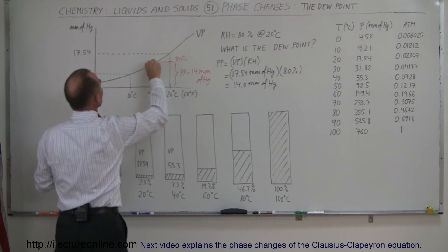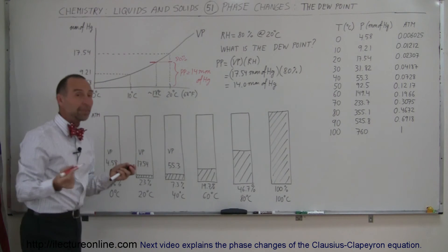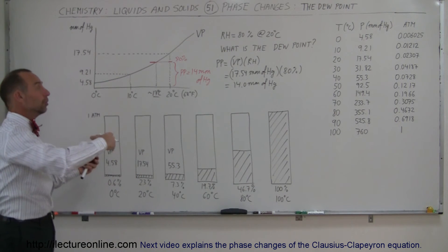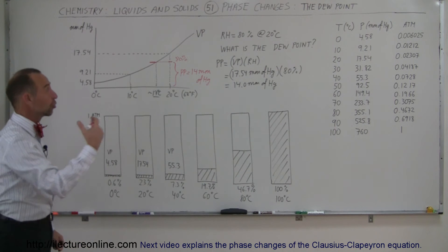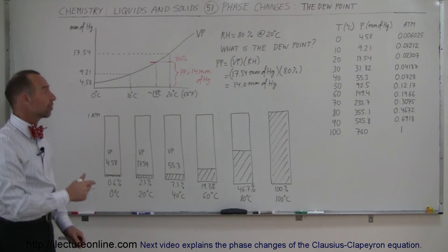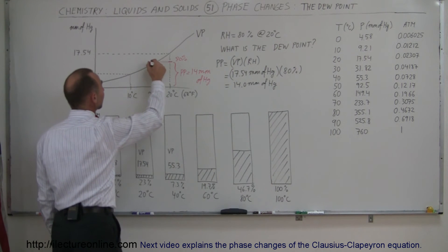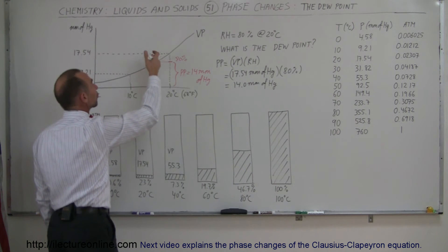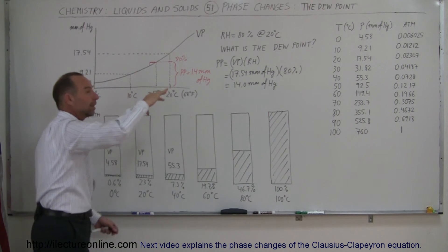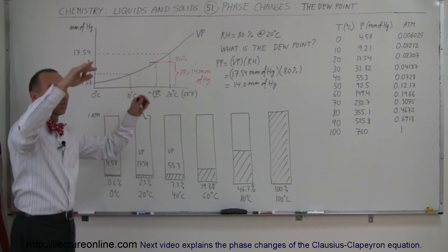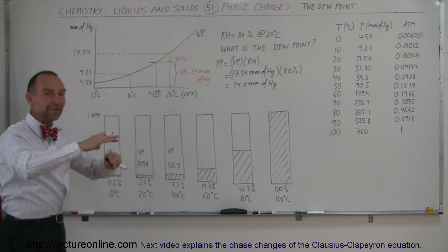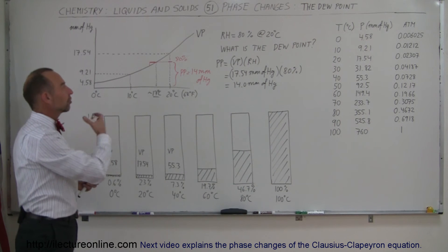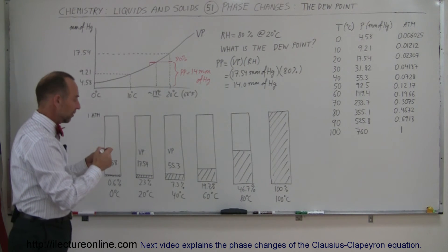The partial pressure is now greater than the vapor pressure, which can never happen. You can never have more moisture in the air than the air can hold — you can never have a partial pressure greater than the vapor pressure. So this additional difference simply means that the water begins to condense and turns from water vapor into moisture, and little droplets form or everything on the surface begins to get wet. That's simply the extra moisture in the air beginning to condense out.